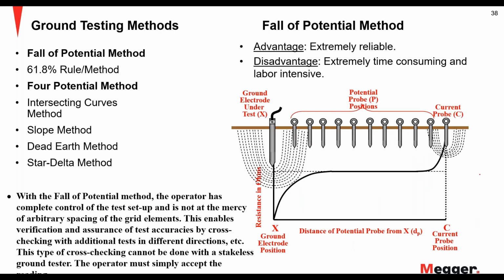Now, how do these methods work? It is typically the fall of potential method that most of the guys use in the field. You have your 61.8% rule, or 62% rule, where you place your potential probe at 62%, somewhere around here. And that's when you will have a constant or true reading that is stable and without the effect of any earth shells of the grounding system itself. And that will give you a true resistance reading of the grounding rod. And you have your 4-pole potential method that has several different methods: intersecting curves, slope, dead earth, and star delta. We don't have enough time to explain all of that, but these are some of the different methods inside 4-pole testing.